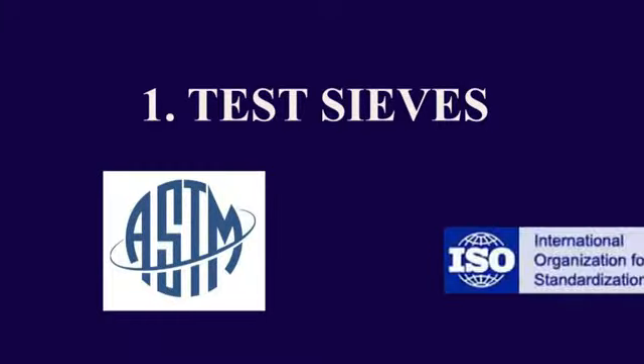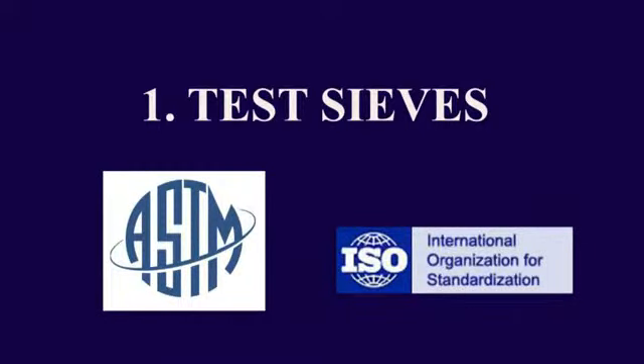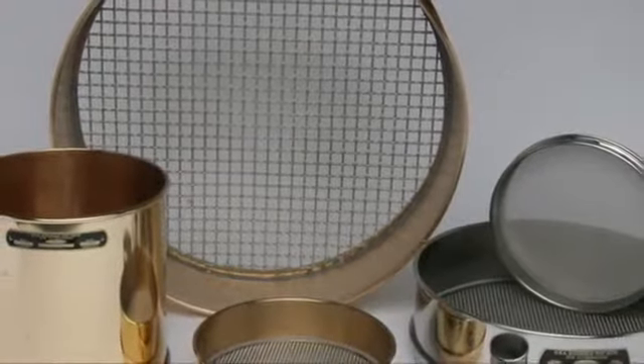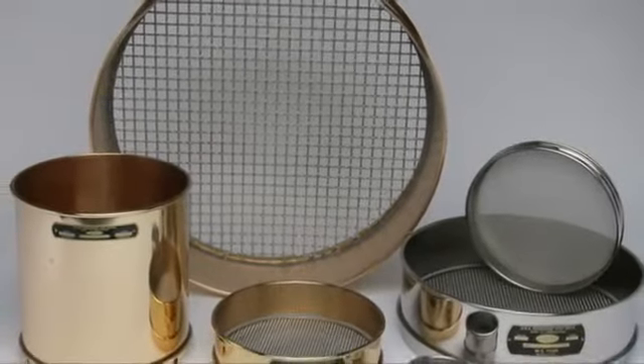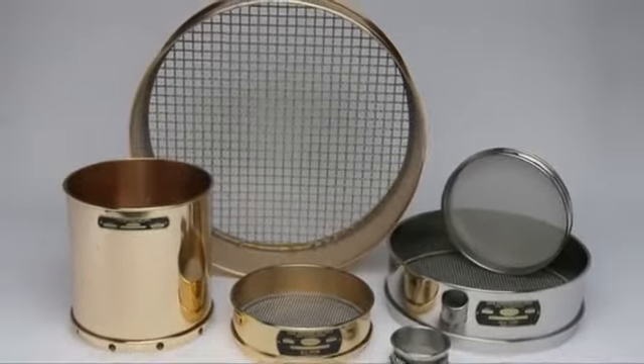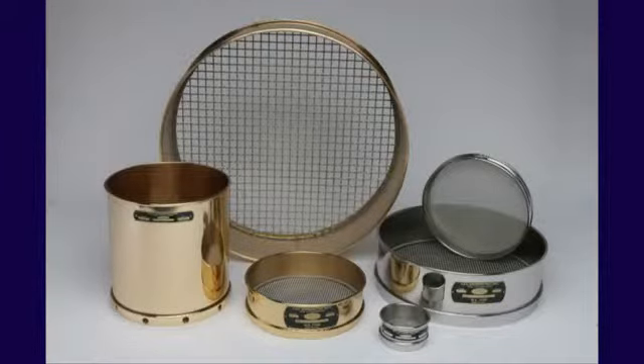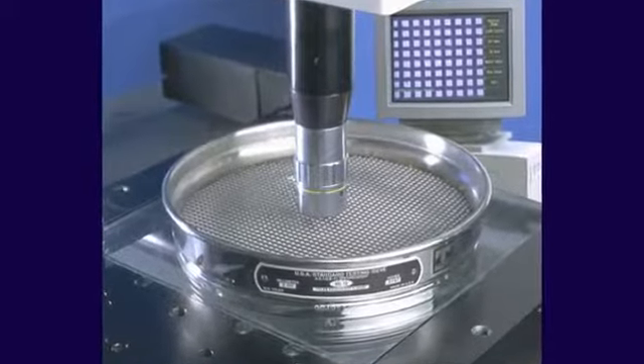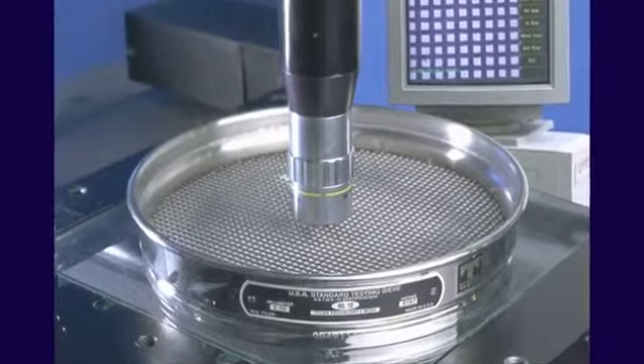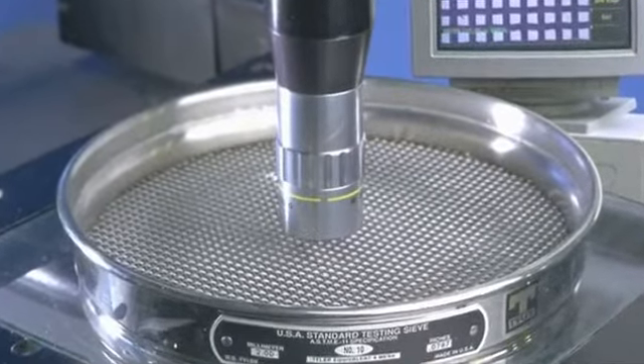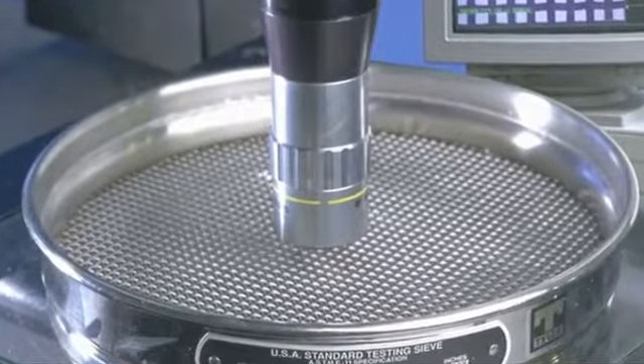Test sieves should conform to current ASTM E11 or ISO 3310-1 standards. Generally, sieves are constructed of brass and/or stainless steel components. Common diameters are 3 inches, 8 inches, and 12 inches, or metric equivalents. Special diameters are also available. Test sieves are available in three grades: compliance, inspection, and calibration. Compliant grade test sieves are primarily used. The sieves can also be examined to verify the openings and wire diameters of the mesh in order to ensure compliance to inspection or calibration grades. These examinations provide NIST traceability.